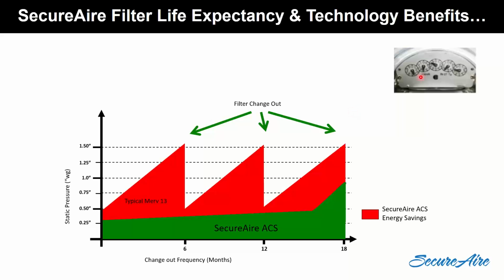If you had Merv 13 filters, which is the bare minimum ASHRAE is going to recommend for catching SARS-CoV-2, you're probably going to have to change those filters every 6 months or so, or at least in this example, right? Because the pressure is going to build up and build up pretty high. And at some point it's so high, we're going to have to change the filter out.